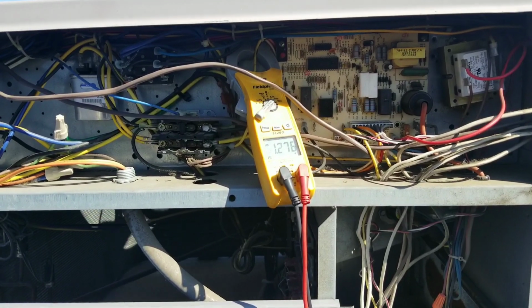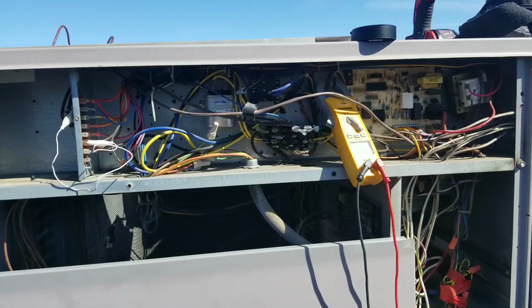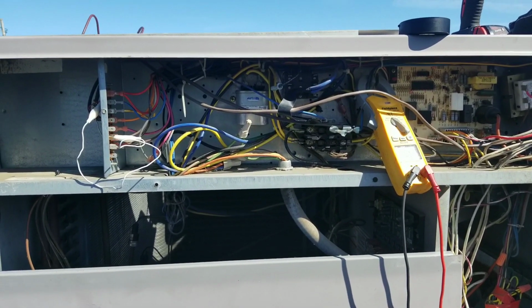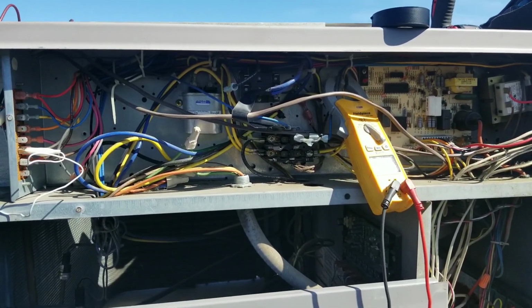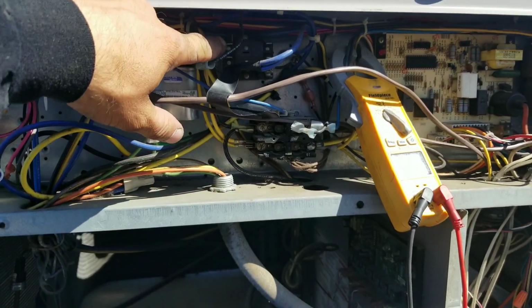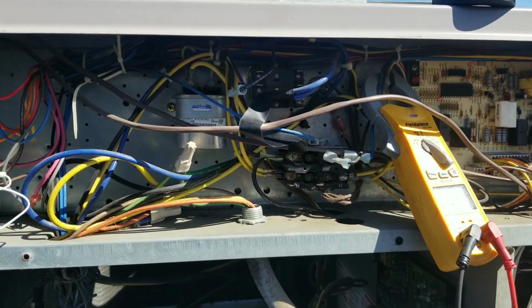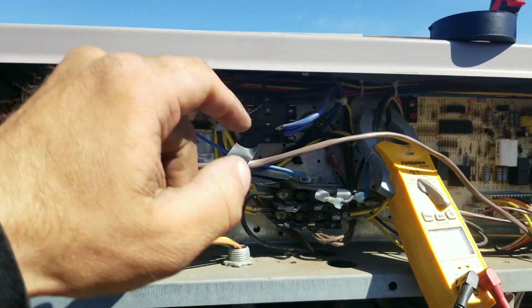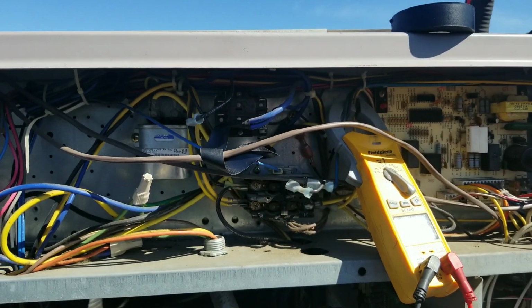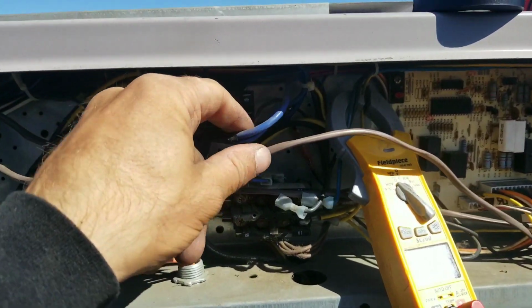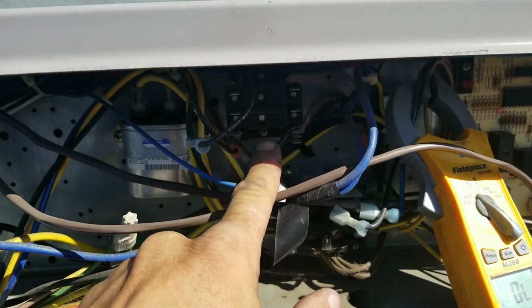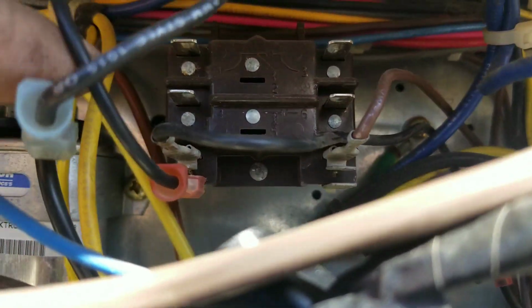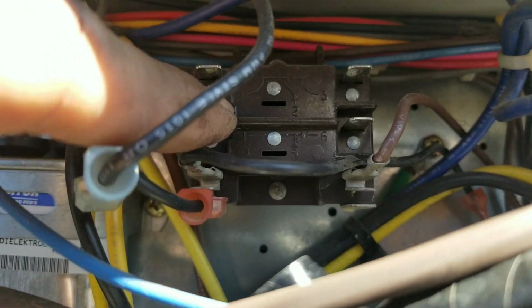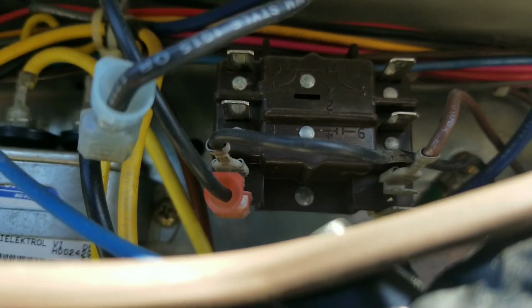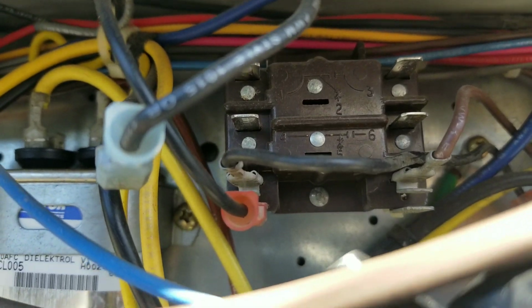Alright guys, let me set this camera down real quick so I can check that motor. I did verify we have 490 volts sitting on the left side on both of these terminals to the switching relay. But on the other side, I wasn't getting proper voltage. So what I'm going to do is check this relay once I have 24 volts going to it. It's kind of bright out here. But I'm going to check this relay across these two terminals, 4 and 6, and 1 and 3, once I get this thing powered up.